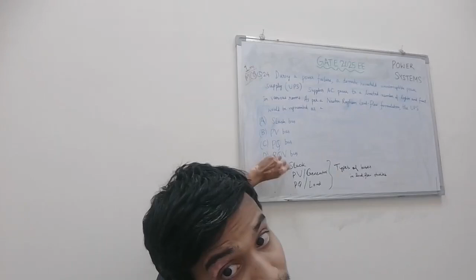It can be considered as a PV bus, but since it has sufficiently large power capacity supplying AC power, that means the load isn't just active power. Fans, being single-phase induction motors, draw reactive power as well during starting. So who is supplying this reactive power? The UPS supplies AC power, meaning both active and reactive power, so it must have sufficient capacity to deliver to all lights and fans combined.